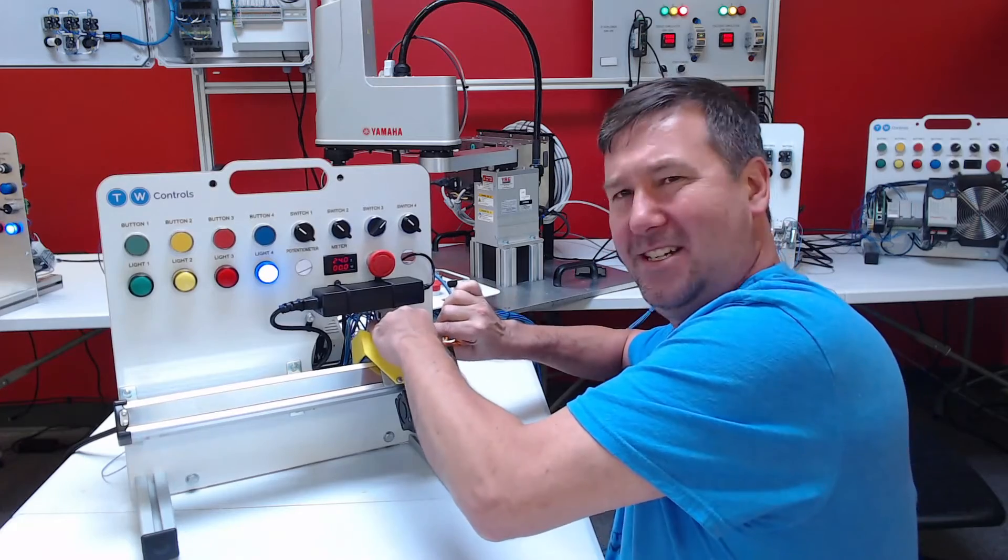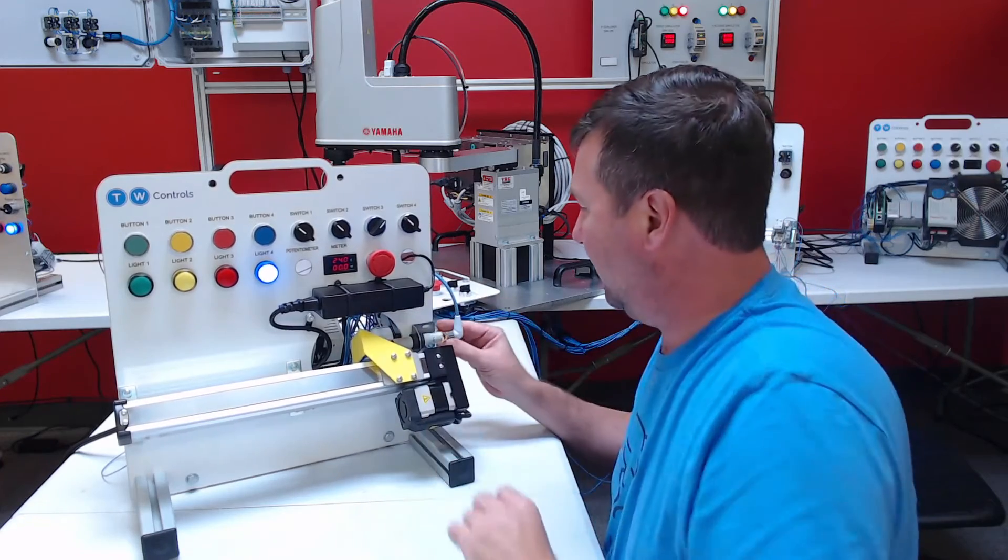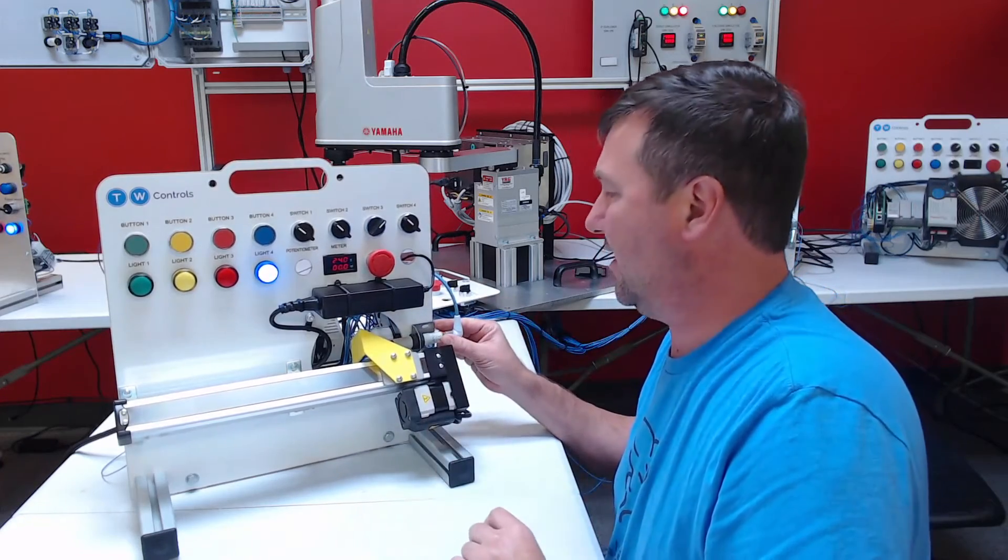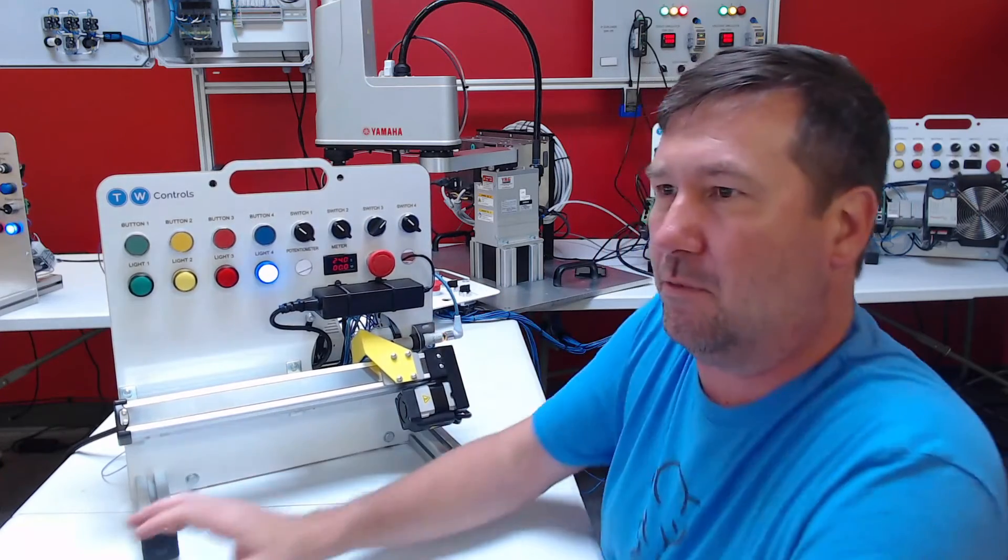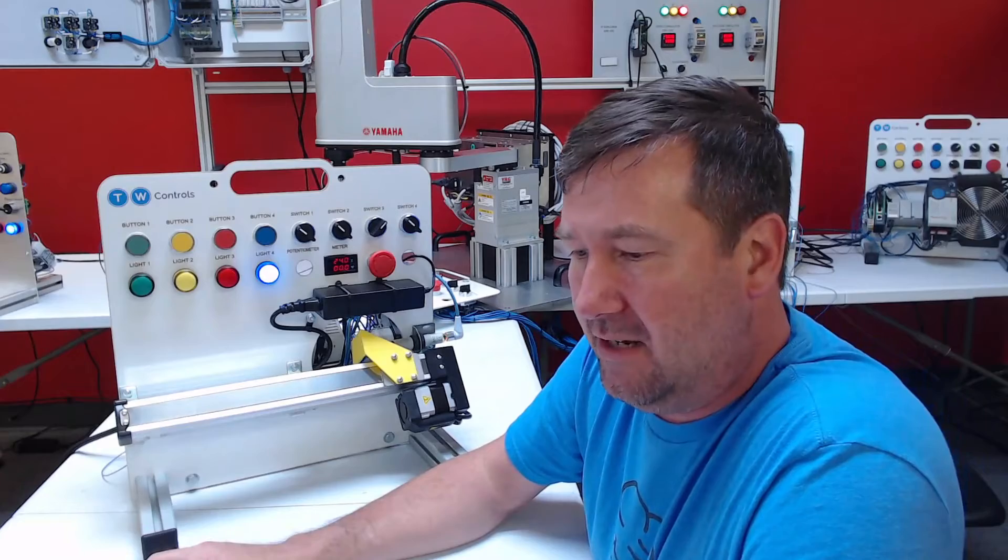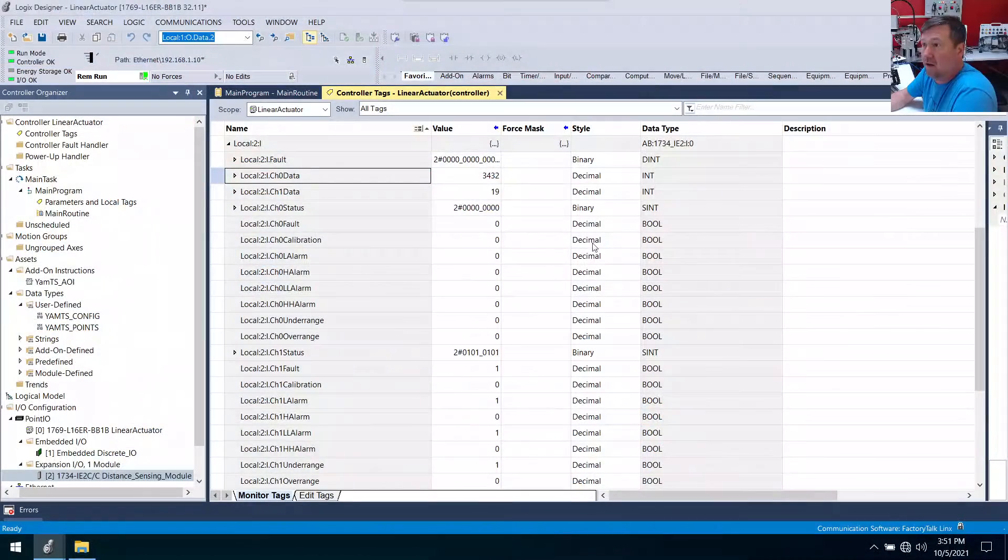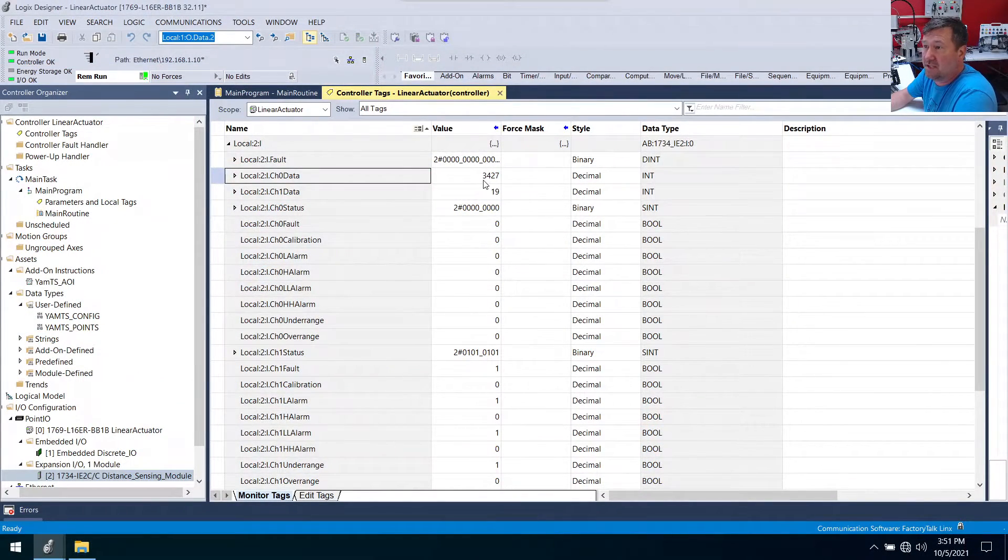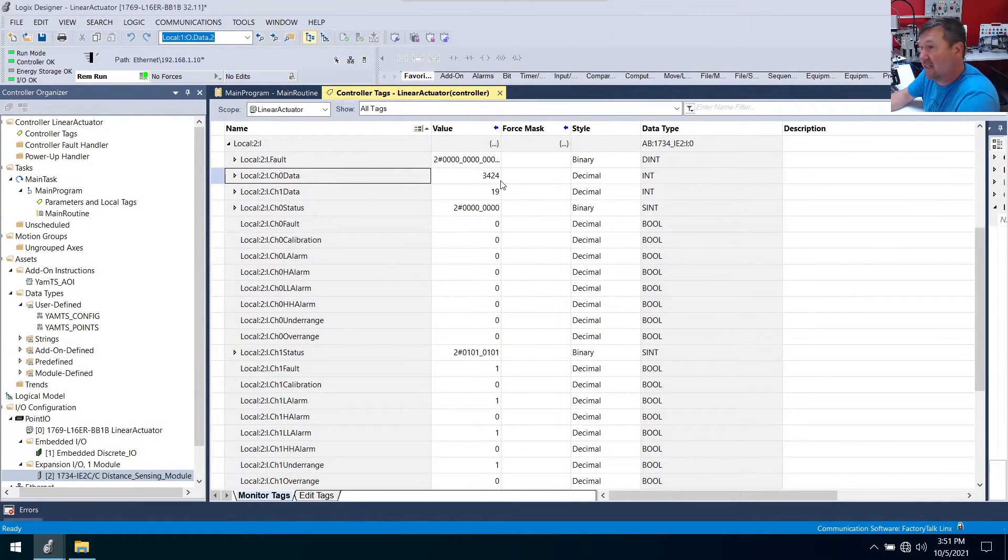Because that's going to set our 4 milliamp value mainly so that we're near the full span of this sensor. Now it already should have that set from the factory, but just in case yours gets out of whack.